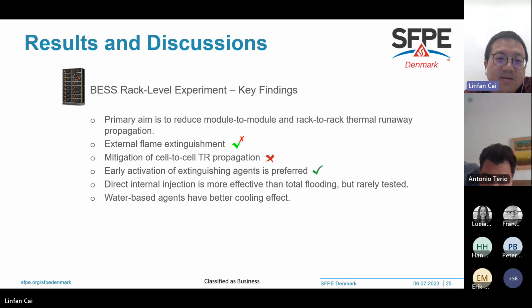Another key finding is that early activation of the extinguishing agents is always preferred. This is to discharge the agents as early as possible, so as to control the fire situation at an early stage instead of at a very late stage, where the thermal runaway has already propagated to the adjacent modules and racks, which makes the whole situation much more difficult to suppress.